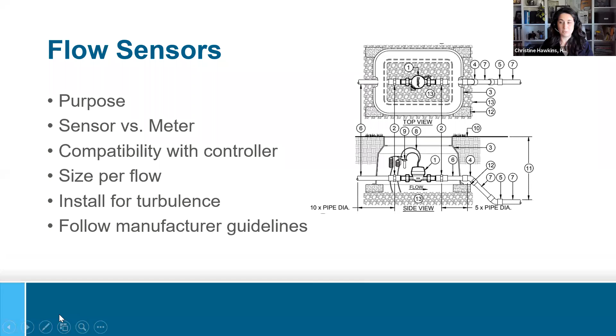And that really takes us to pipe size. Regardless of the type, size your flow sensor for the expected flow range you want to read, not the pipe size of your main line necessarily. This is a tough one for designers and contractors to really understand. Just like sizing your valves, every manufacturer will have a flow chart or spec that shows the range of flows their sensor and their controller can accommodate. Lastly, make sure you're familiar with those manufacturers' guidelines. Many will require particular wire, often shielded cable, and most use the 10 diameter upstream and 5 diameter downstream rule. We'll look a little bit more closely at this detail to show you what I mean.